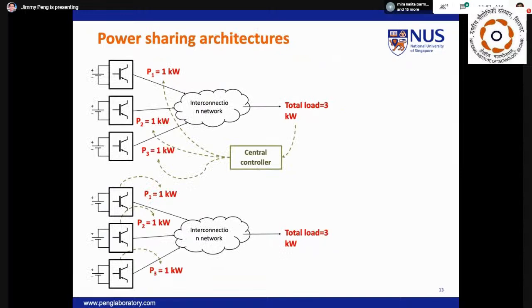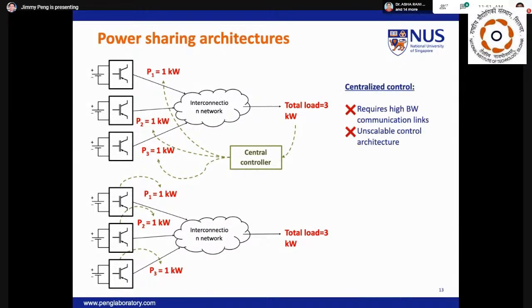So in the first scenario, shown on the top, a centralized control has been implemented. In essence, each inverter will dispatch its generation output based on commands given by the central mainframe. This is a typical architecture used in the conventional power grids, but may not be suitable for microgrids due to the required investment cost. Now, to establish a centralized control requires high bandwidth communication links, and the required control architecture is not scalable when more equipment are integrated into the microgrid over time.